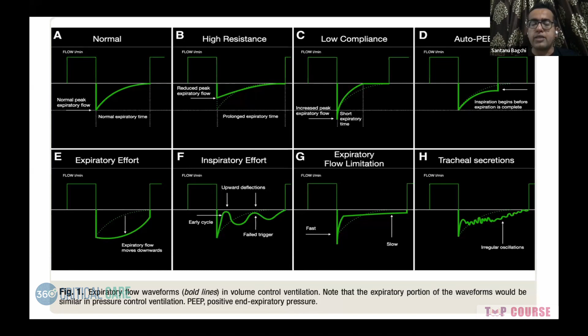And if the patient is having some inspiratory effort, that will also be there in the expiratory graph as upward indiscriminate deflections. Now coming to the inspiratory flow waveform, it's a square waveform in volume control. It can be a descending waveform in volume control, and on the other end, in pressure control mode, the standard is the decelerating flow.